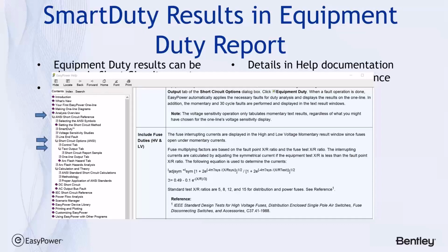Good question. Chuck's asking, so the fuse manufacturers promote the up, over, and down method to reduce available fault current using their fuses, but we cannot use this according to NEC, am I thinking correct? The answer is yes, and I'll touch on that a little bit later. And where is the up, over, down useful? Chuck, you're about 2 slides ahead of me, so hang on to that.